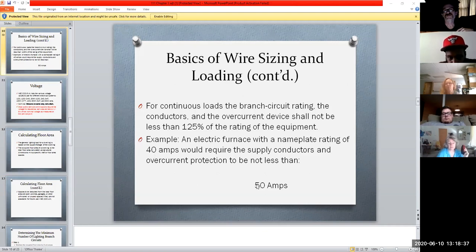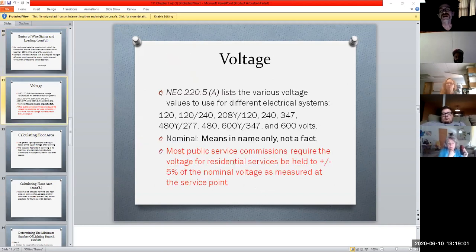So we go, oh, 40 amp rating, but we need a 50 amp breaker. Is it going to pull 50 amps all the time? No. But when it's under load and it's running hard and heavy, it'll probably pull 50 amps for a certain amount of time, but it's considered continuous duty. So it does change the way we have to look at a circuit breaker or circuit delivery. So with the NEC, again, we have tables. We can look these up in charts and they'll have ratings for it. We can look and go, oh, 50 amps, they already have the amps multiplied by 125%. We'll go, oh, well, we need this breaker size here.